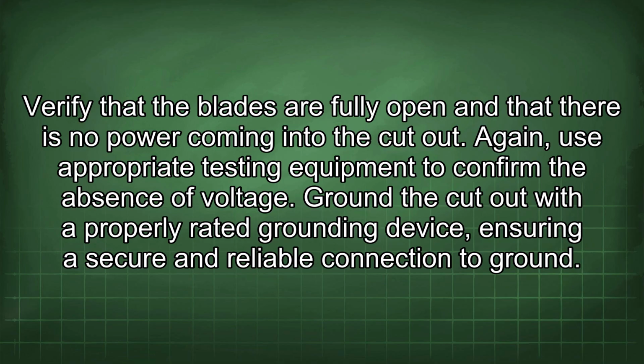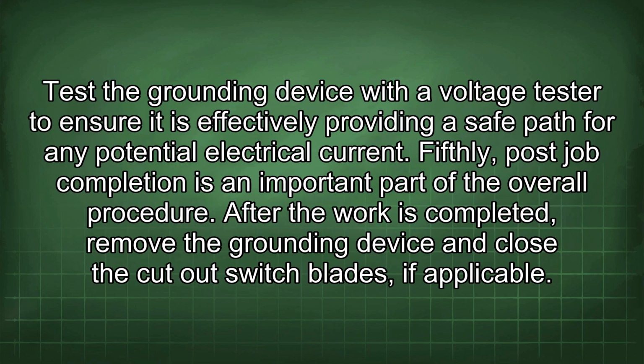Verify that the blades are fully open and that there is no power coming into the cutout. Again, use appropriate testing equipment to confirm the absence of voltage. Ground the cutout with a properly rated grounding device, ensuring a secure and reliable connection to ground. Test the grounding device with a voltage tester to ensure it is effectively providing a safe path for any potential electrical current.